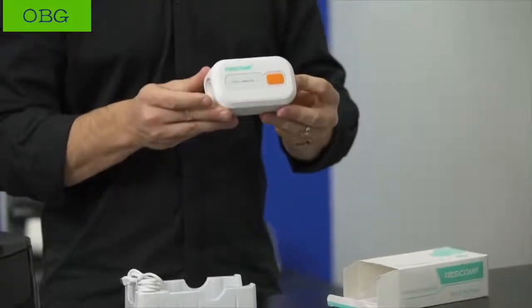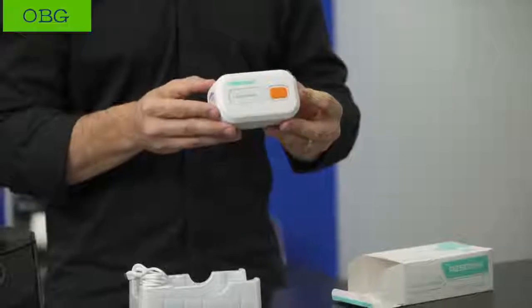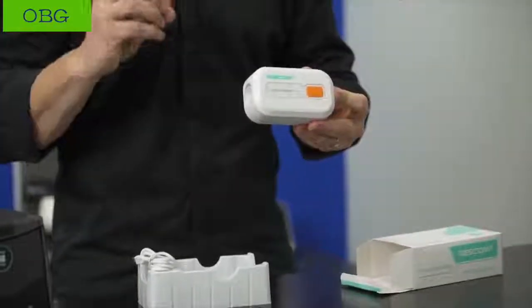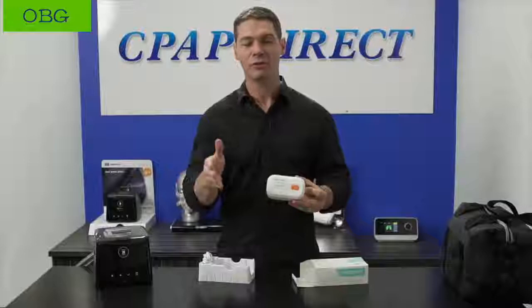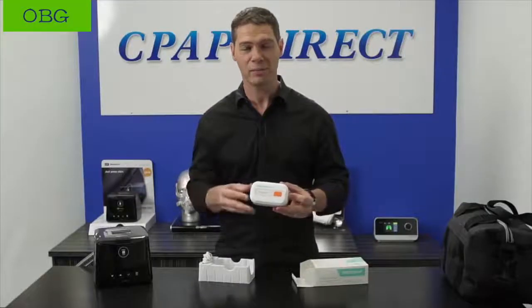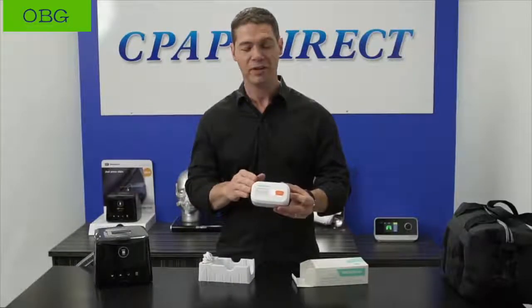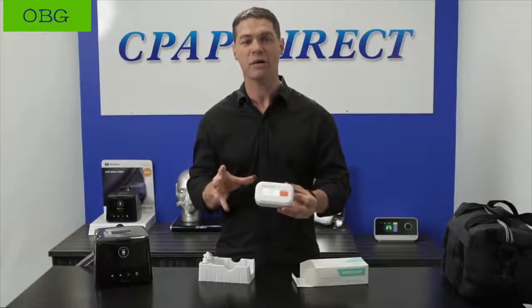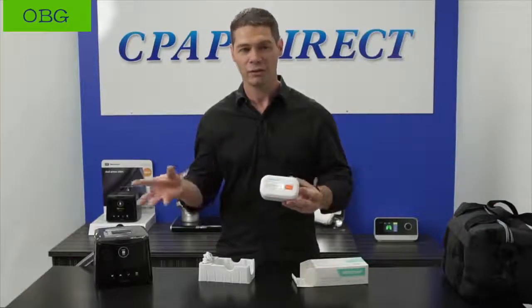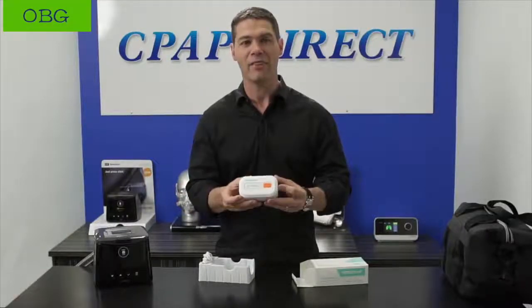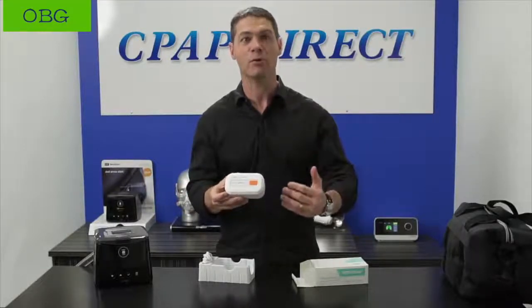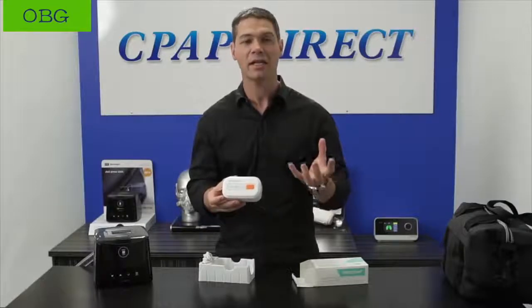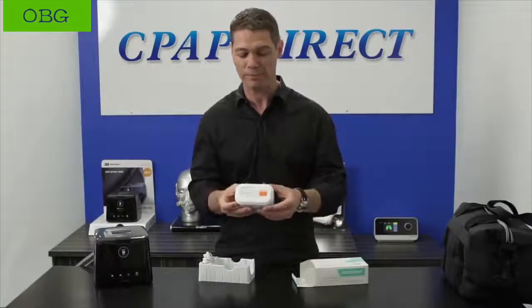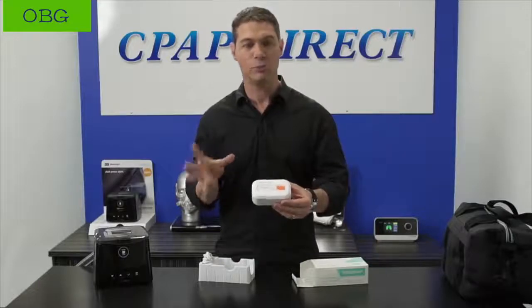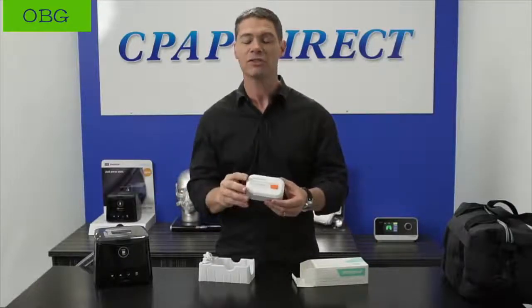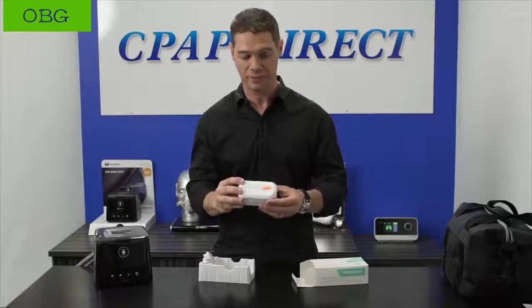Once activated, this machine produces 30 minutes of ozone, followed by 5 minutes of pure air to blow out the ozone smell. If you've ever used an ozone generator before, you know it has a unique smell. This ozone disinfector is a slow release ozone. It's much longer than a lot of the ozone generators out there on the market, and that is designed really to minimize the smell, but also really effectively clean or disinfect your Cpap equipment. The last 5 minutes is just pure air to blow out that residual smell, so it's not offensive when you go to use your machine again.